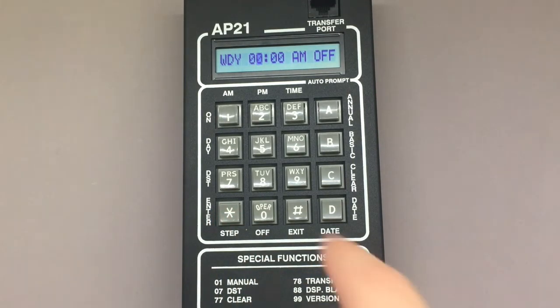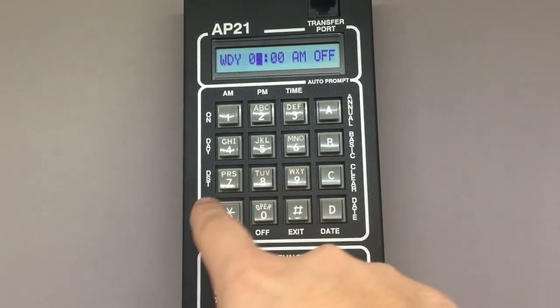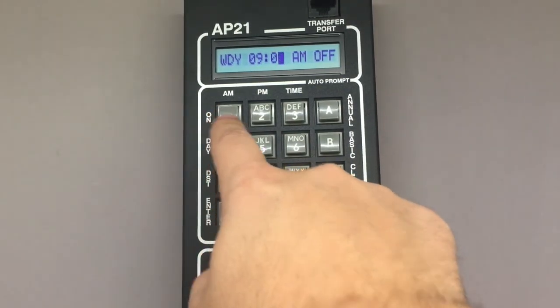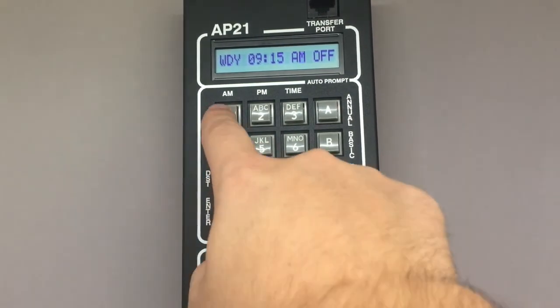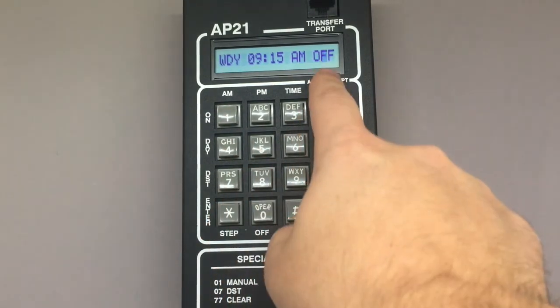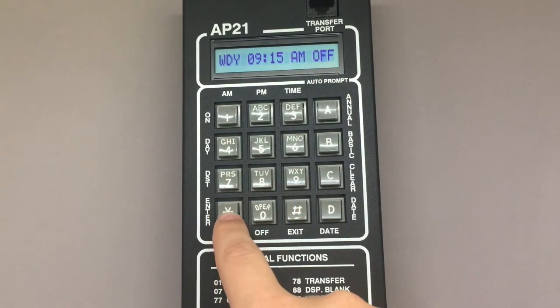I'm going to press 09 star, 15 star, 1 for a.m., star, and since I want the flashers to turn off, I'm just going to leave this designator alone and press star.